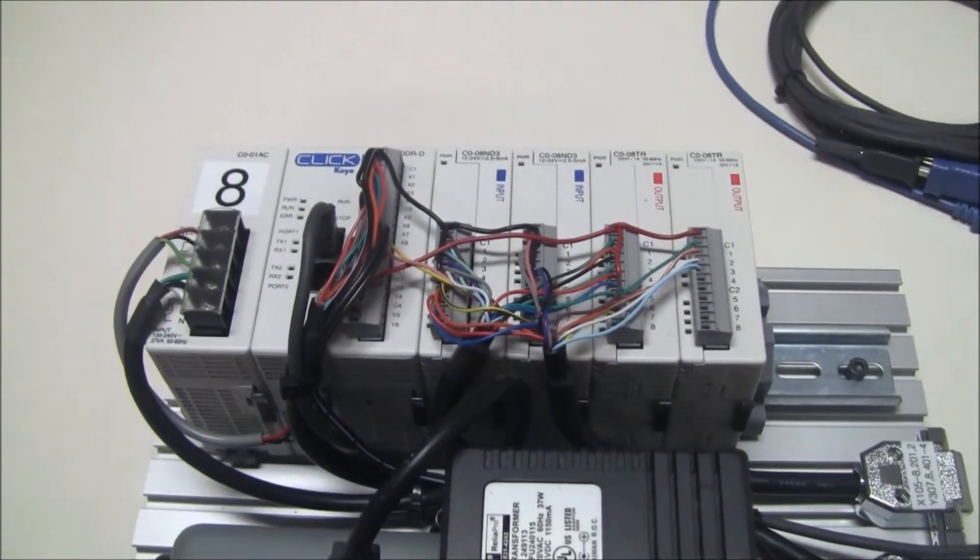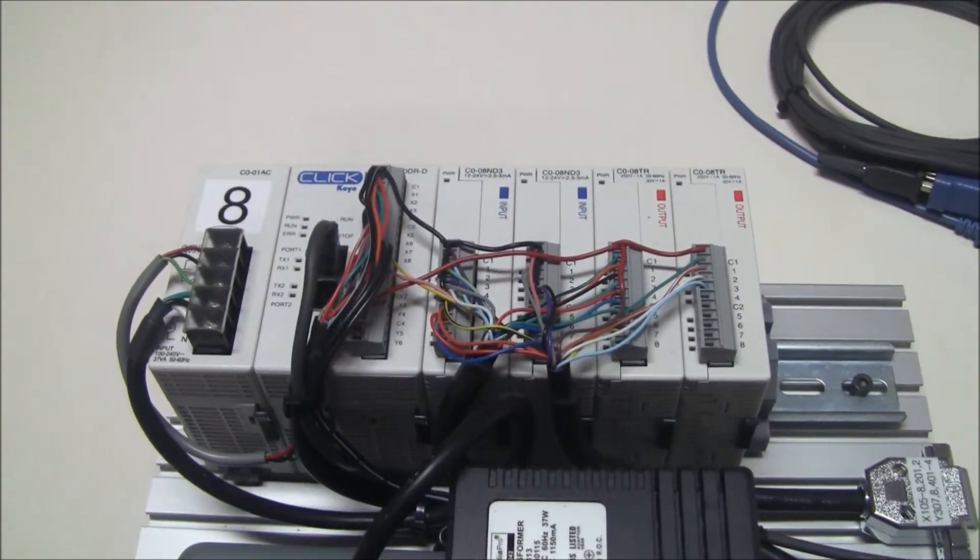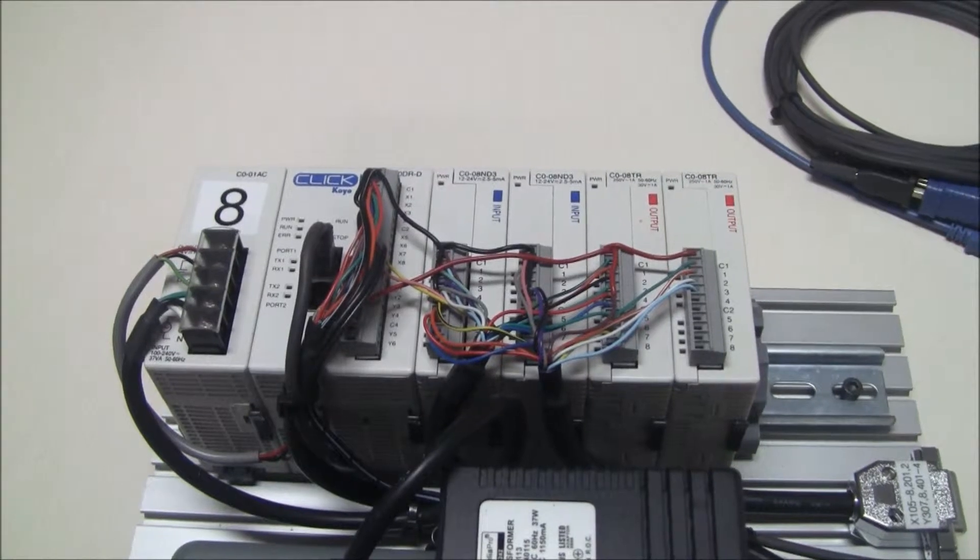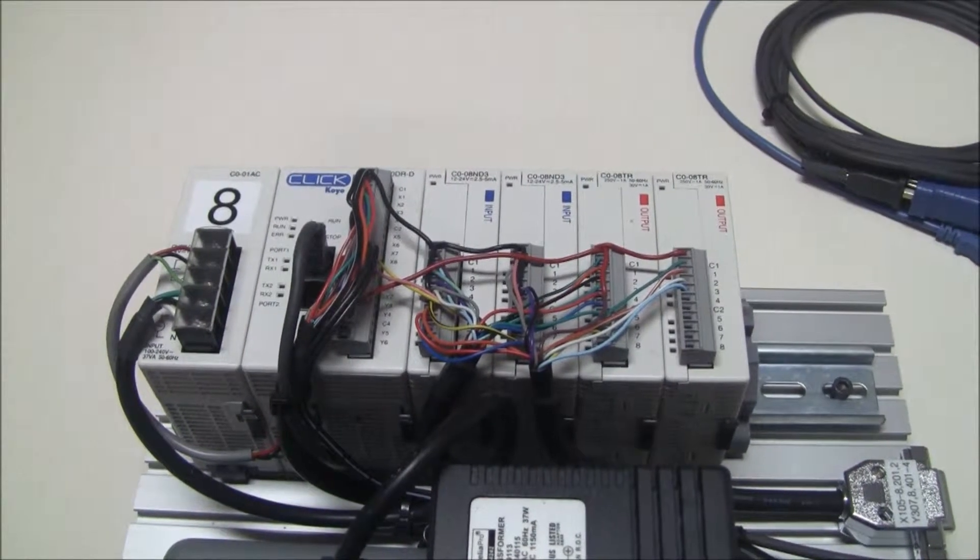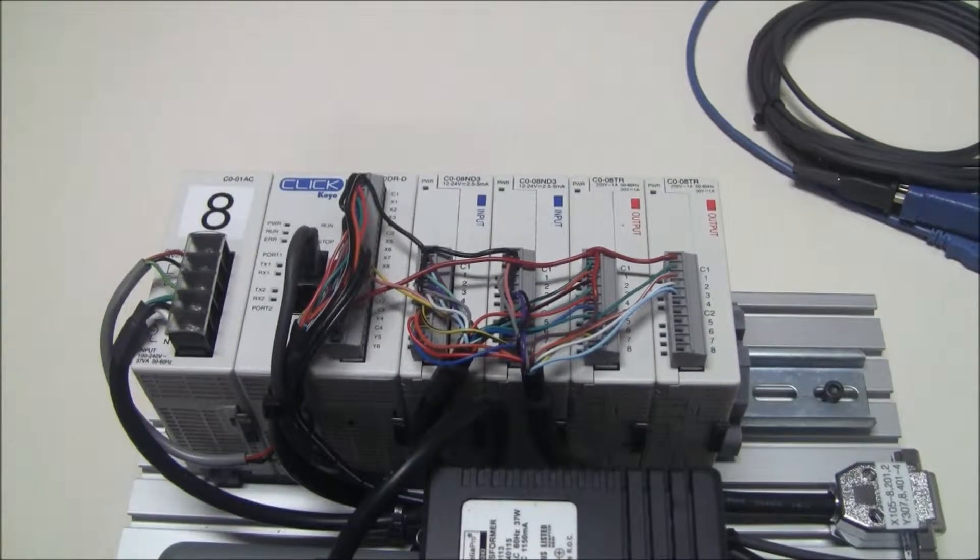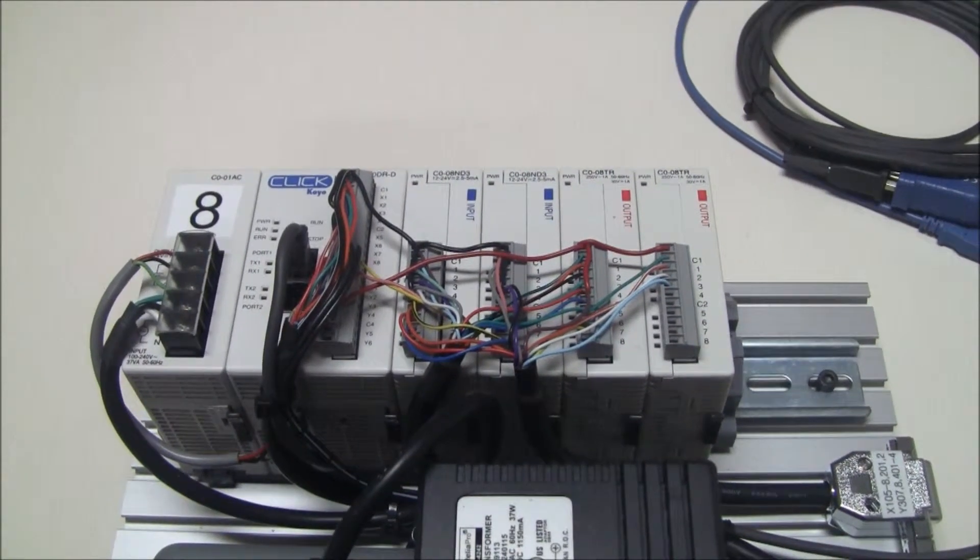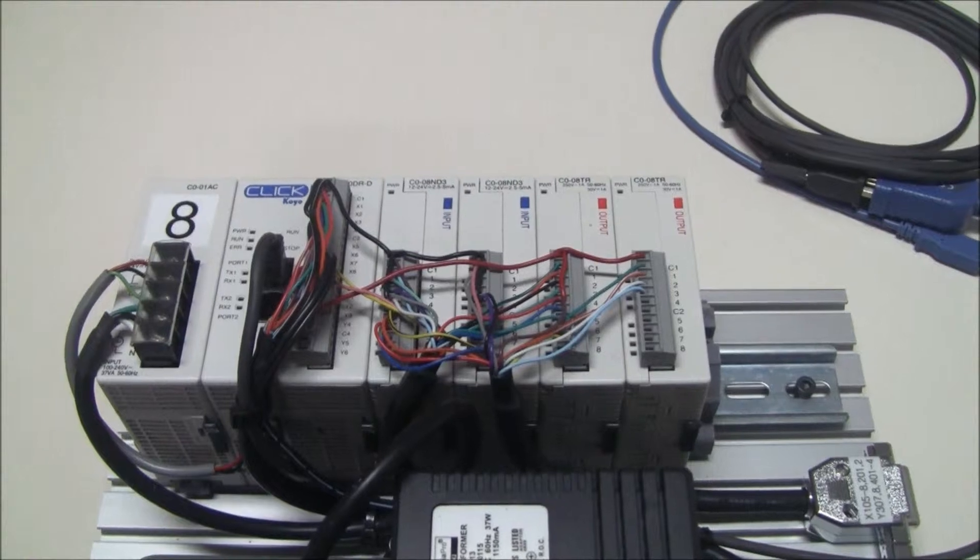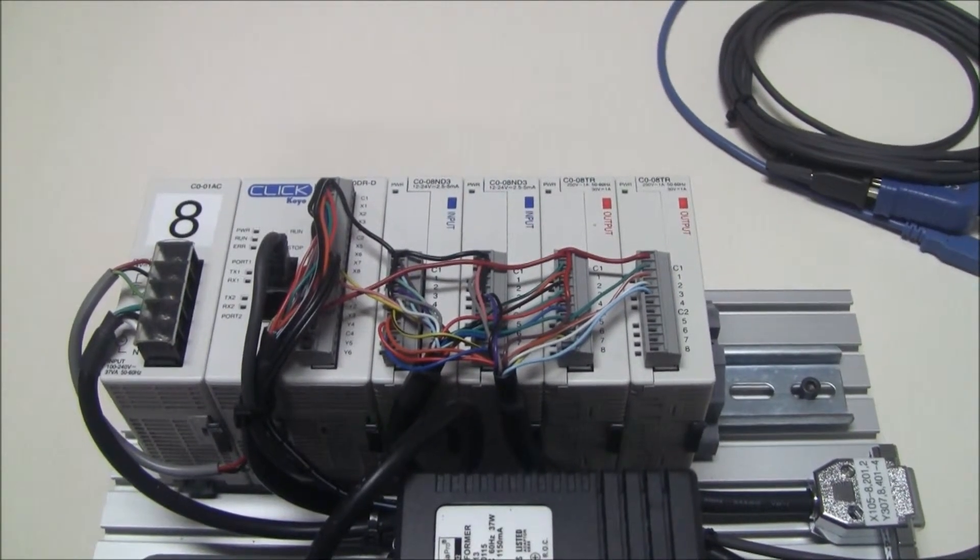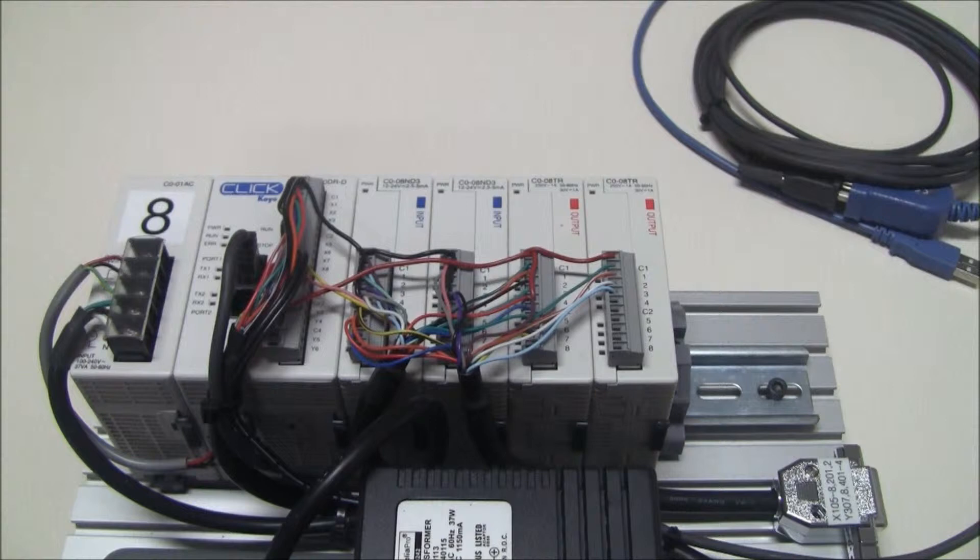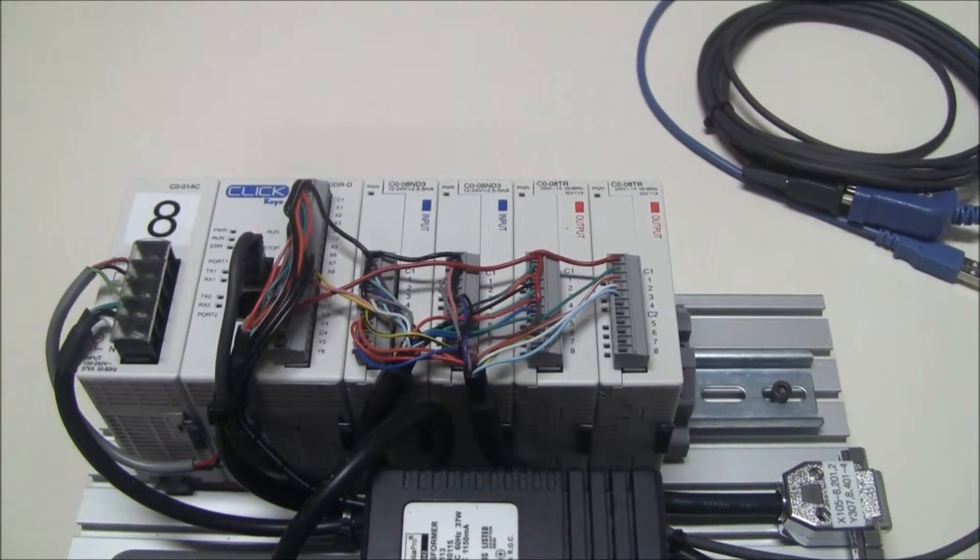So with this PLC, I have on the far left the power supply module. So in is coming my AC power, and out of it is coming the 24 volt DC to power the processor module. Immediately to the right of the power supply module is the CPU, the processor, and this one is a little bit special. It does contain some IOs, some inputs and some outputs.